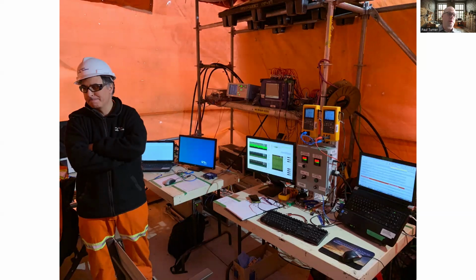One of the contract requirements was to apply an open circuit test at full speed and a short circuit test at full speed—basically to apply a full short circuit to the machine and see how the protection systems react. Now, I'd never done one of these tests before, and these are hydrogen-filled units, so if you get this wrong, the machine will explode.